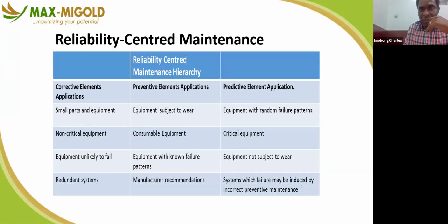Then for the predictive element application, these are equipment with random failure patterns. You can't really say, oh, this equipment will fail tomorrow. It's supposed to fail maybe in 6 months, but in 3 months you're having issues. So what you do is put a monitoring device around the equipment, and then you can take informed decisions based on the data that you have generated. Then critical equipment, you don't need to be touching such equipment anyhow. The best thing to do is to put devices that can give you readings, like maybe electrical panels, that will give you indicators and can, at some point, say, oh, we need to work on this, we need to change this, we need to do something about this equipment.